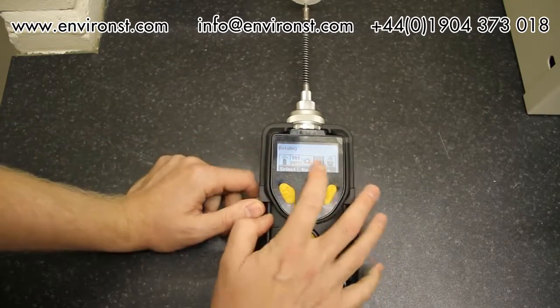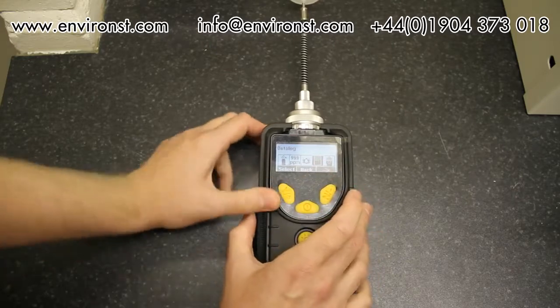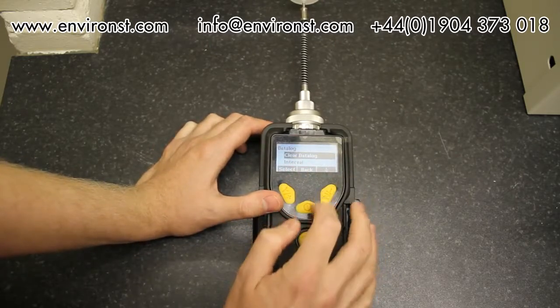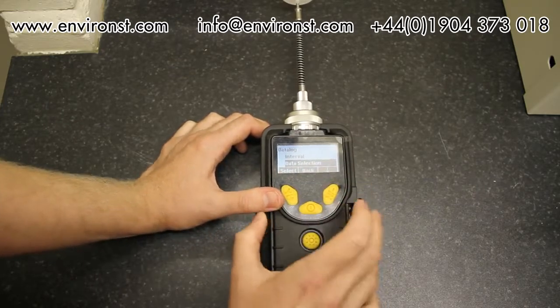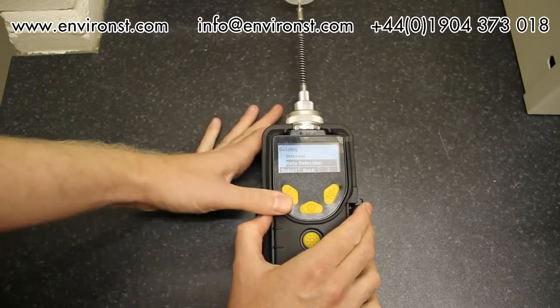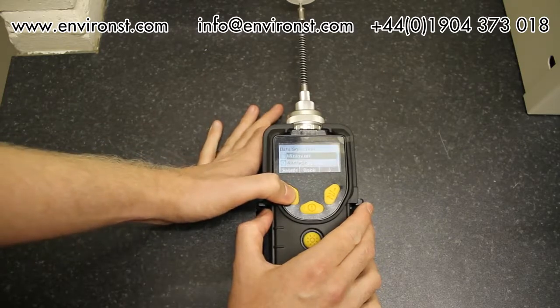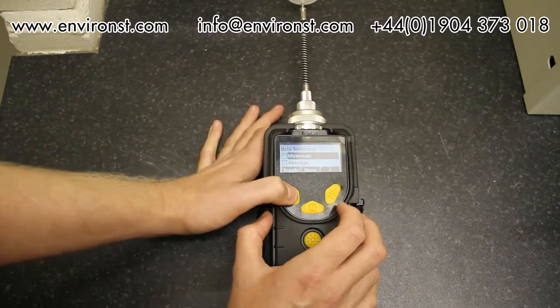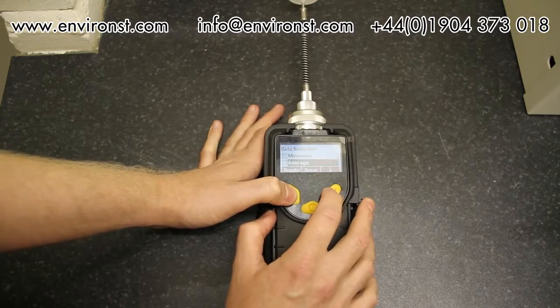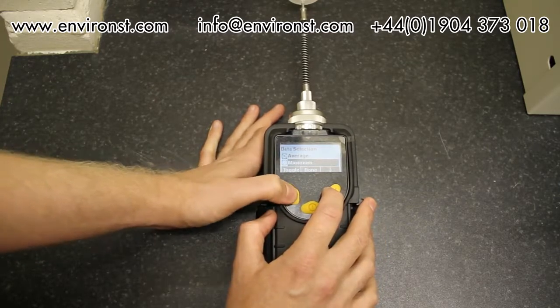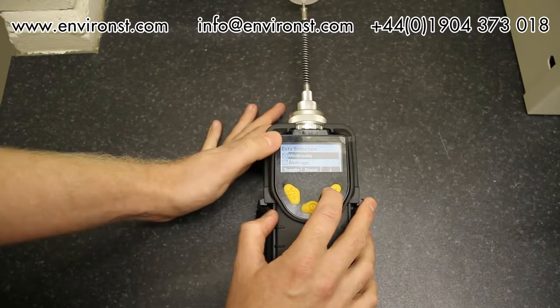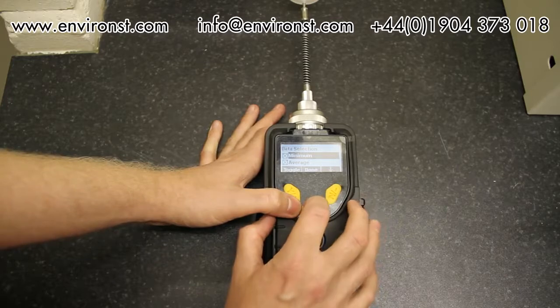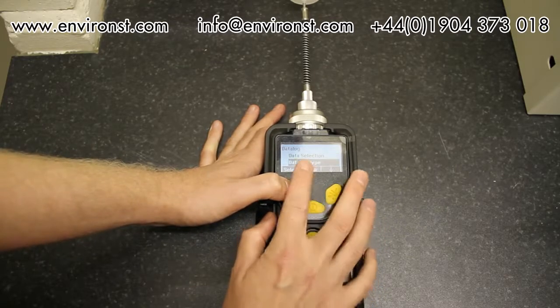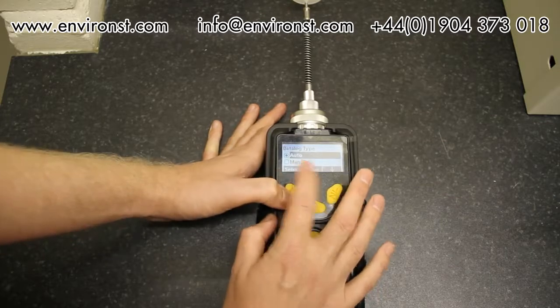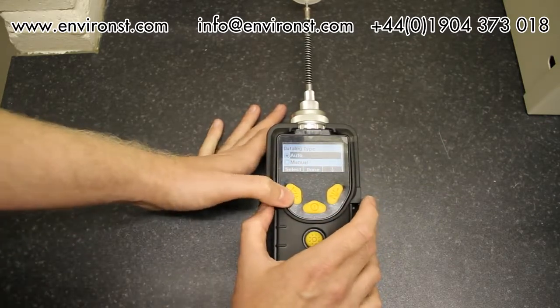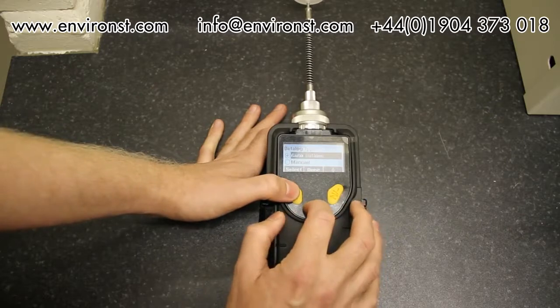So if we go back, we now get to the data logging section. So if I go to the data log, I can clear the data log here, I can set the interval, I can select the data that I want to record. So if I just pop into that momentarily, so I've got minimum values, so I'm going to actually turn that on. So minimum values, average values, maximums, we'll toggle that on, and that's all the data logging that we can have. So if I save that, so data log type, automatic or manual, so that's the difference between automatically data logging or I have to turn it on.